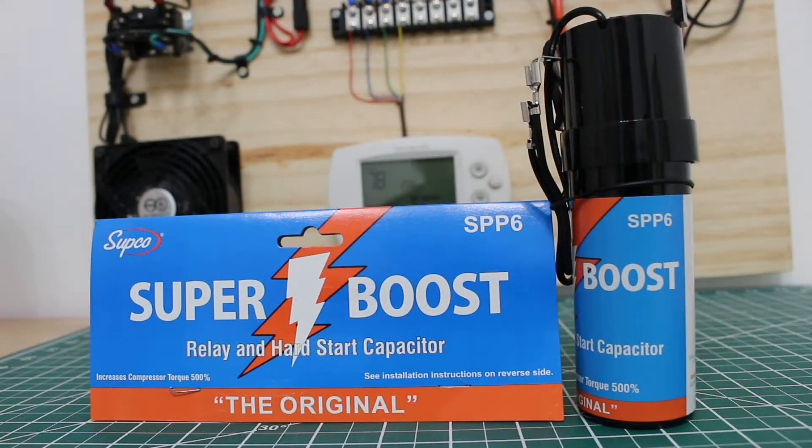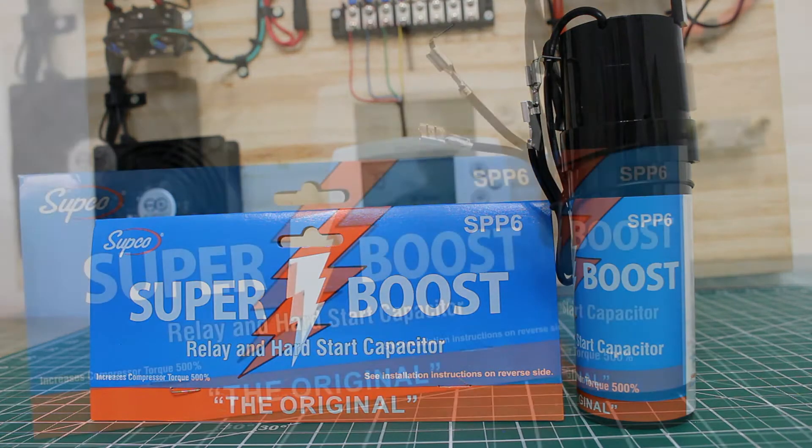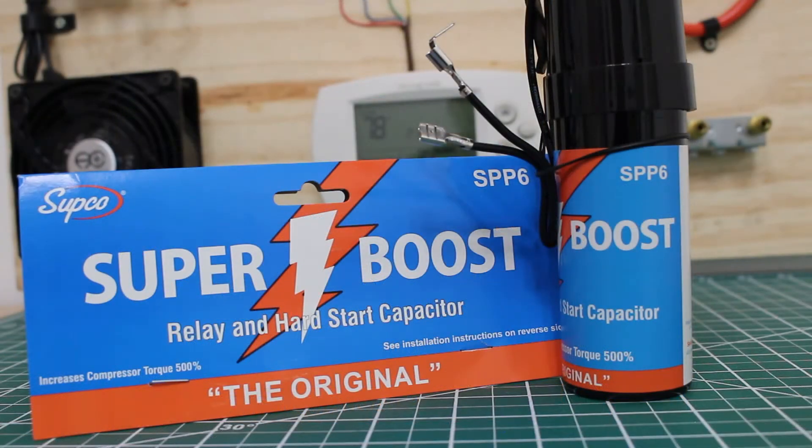This is the Supco Super Boost, model number SPP6. It is a relay along with a hard start capacitor built into one. It gives an additional starting torque up to 500%, so for those compressors that are having trouble to start, this may be your solution. This can be used for all single-phase 120V to 288V units, ranging from half horsepower to 10 horsepower.